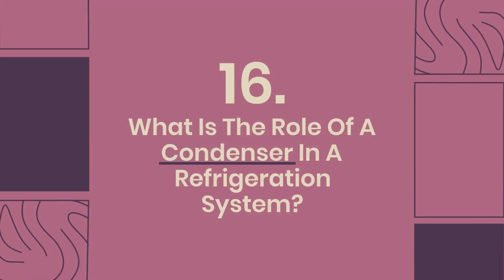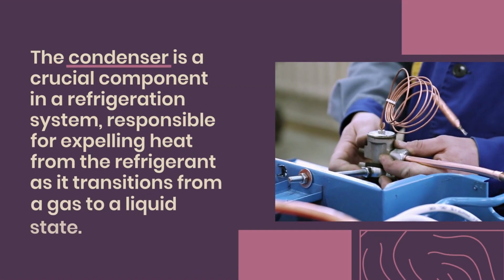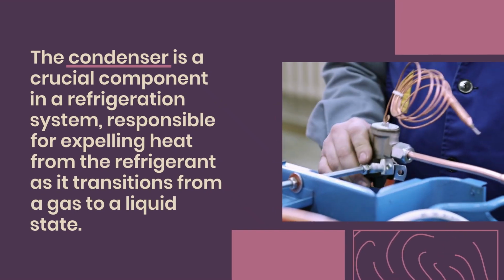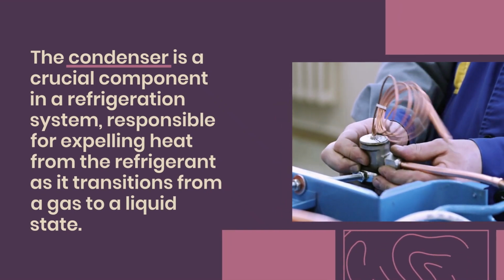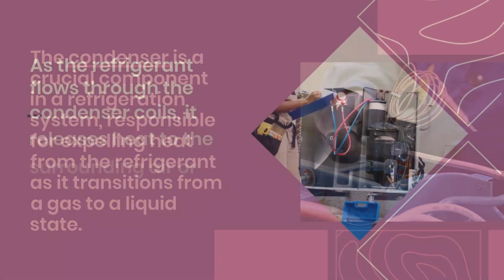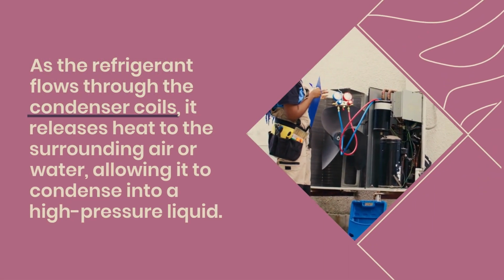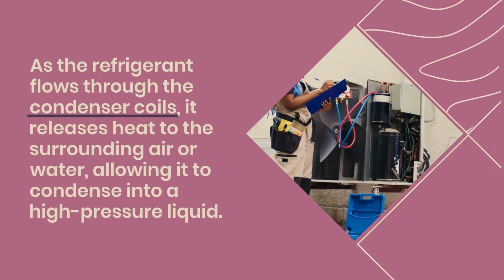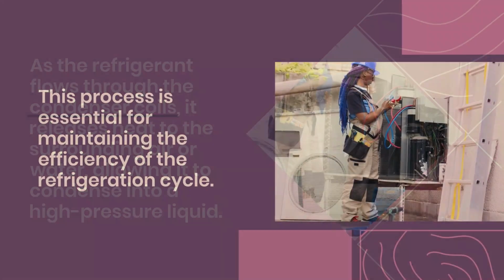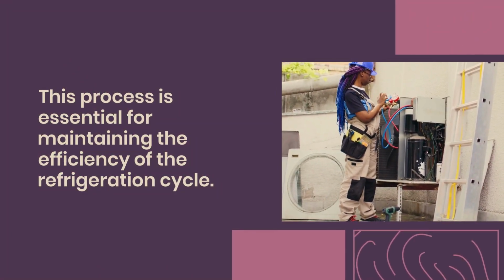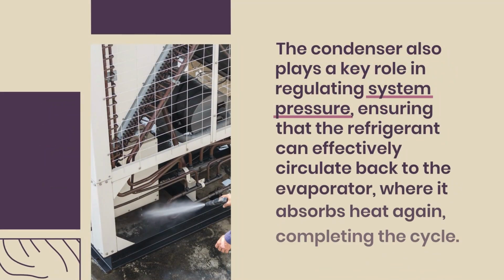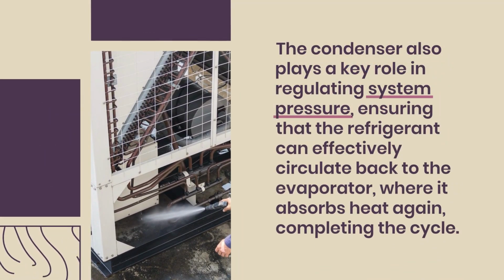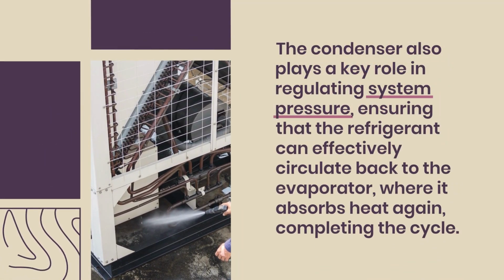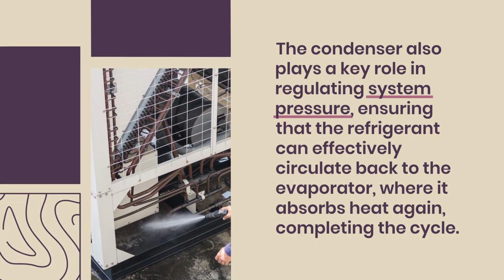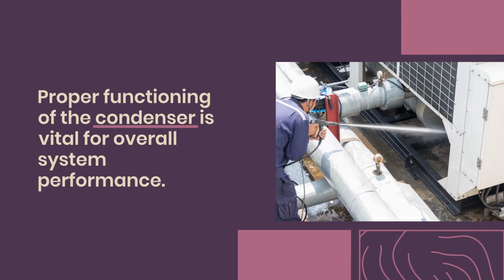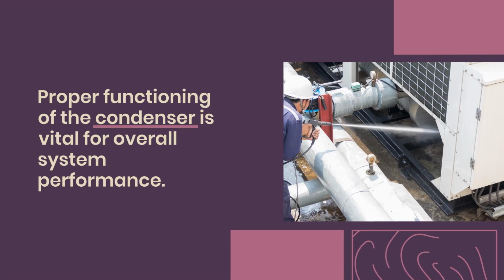16. What is the role of a condenser in a refrigeration system? The condenser is a crucial component in a refrigeration system, responsible for expelling heat from the refrigerant as it transitions from a gas to a liquid state. As the refrigerant flows through the condenser coils, it releases heat to the surrounding air or water, allowing it to condense into a high-pressure liquid. This process is essential for maintaining the efficiency of the refrigeration cycle. The condenser also plays a key role in regulating system pressure, ensuring that the refrigerant can effectively circulate back to the evaporator, where it absorbs heat again, completing the cycle. Proper functioning of the condenser is vital for overall system performance.